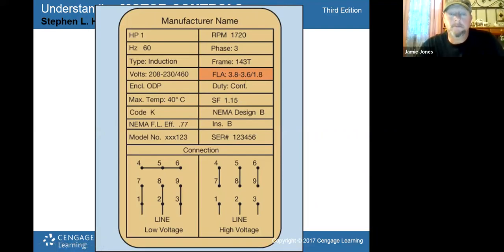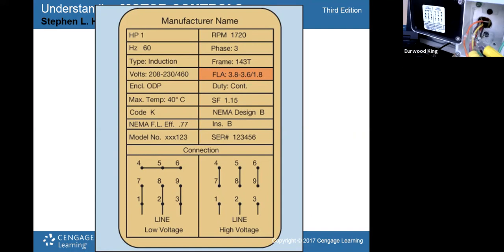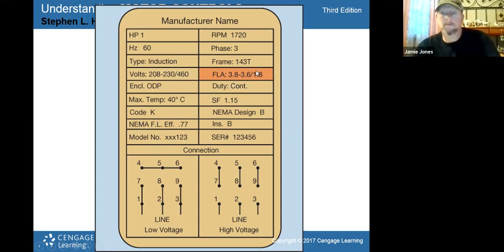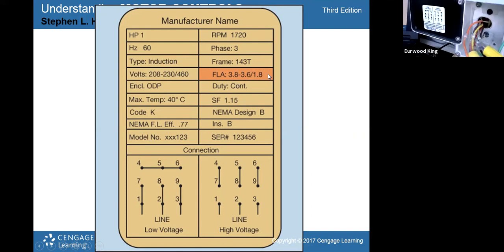Is it the same number if you multiply 230 times 3.6? Yeah, right. So what we're getting at is this. Some people think that when you double the voltage and the amps goes in half, they're going to get by running the motor cheaper. But you're not. You're still paying the power company the same for wattage, for the kilowatt hours you use. Volts times amps equals watts, and the wattage consumption is the same whether you're at 230 or 460. The only advantage of going 460 is that you can use a smaller wire size. Whenever you go to high voltage, your wire size can go down.